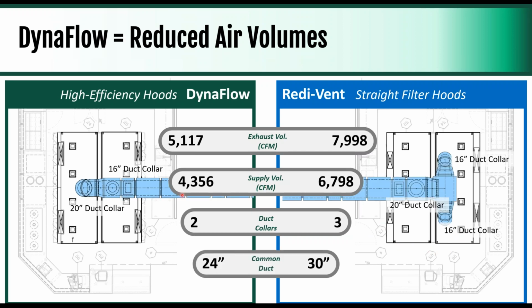And then lastly, the common duct size difference between the two. For the Dynaflow hoods, you're looking at 24-inch diameter. For the non-high efficiency hoods, you're looking at a 30-inch diameter. That is important both in terms of the space that it takes up, but also in terms of the cost to put in the ductwork, as well as fire wrapping that ductwork if it is in an area that needs to be fire wrapped.